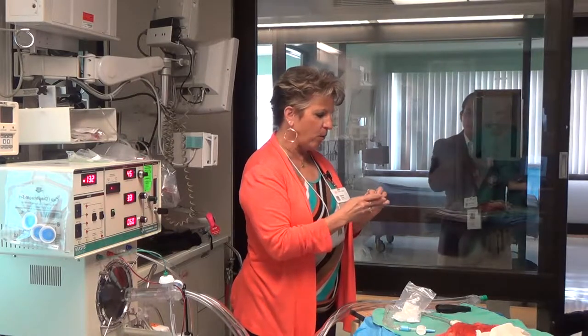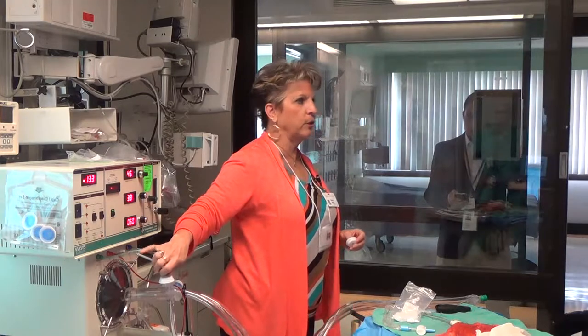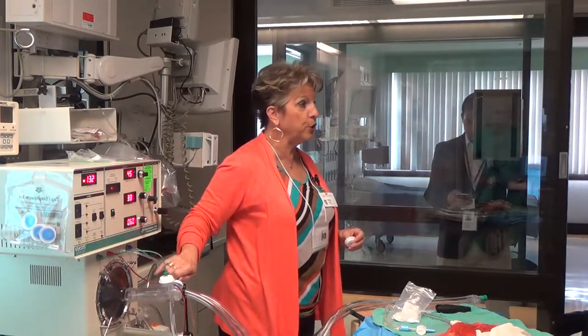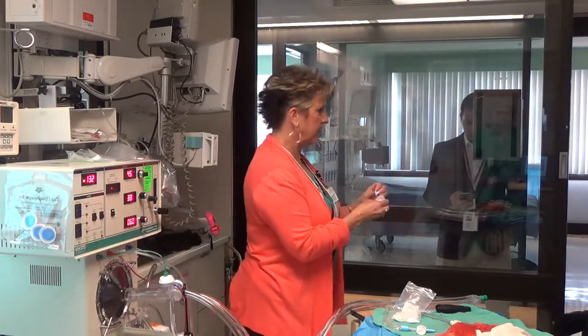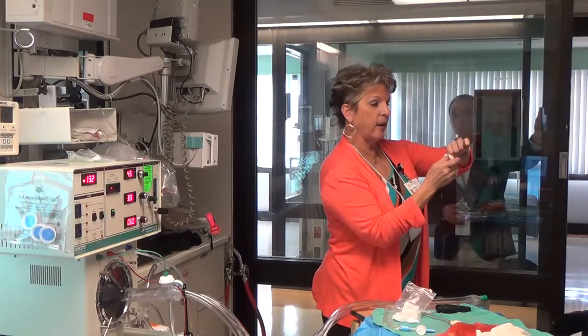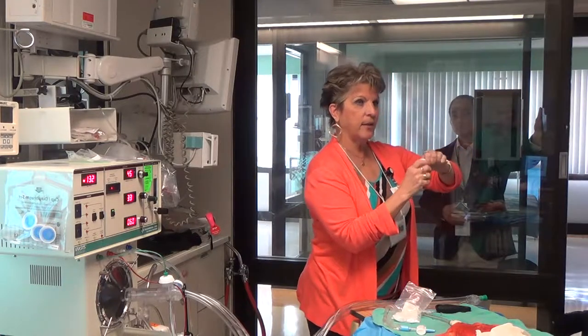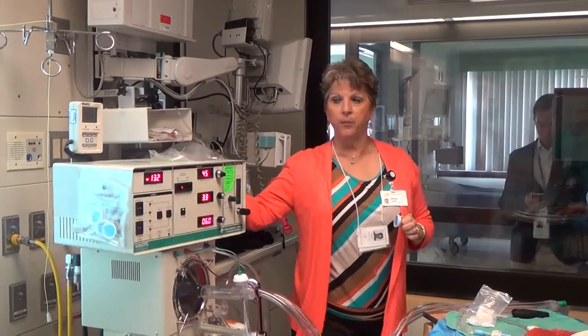But right now, when you guys do your vent check, do you check your Luer locks, your Luer lines? No. I would encourage you to, because if they are spinning, it means that this little piece has popped out. So it's sitting there, but I can spin this. Okay? So you're going to see your mean airway pressure dip a little bit.